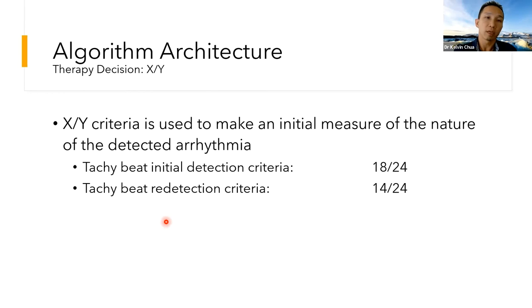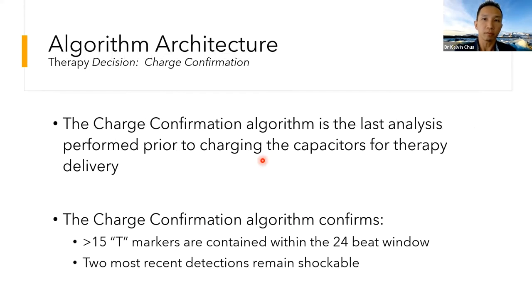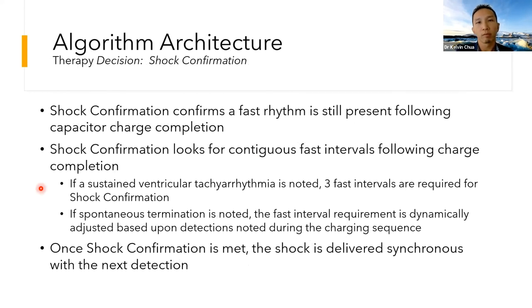After delivering therapy, the redetection criteria is 14 out of 24. Shock confirmation also confirms that a fast rhythm is still present following capacitor charge completion, and it looks at three fast intervals. If spontaneous termination is noted, the fast interval requirement is dynamically adjusted upon detections during the charging sequence.